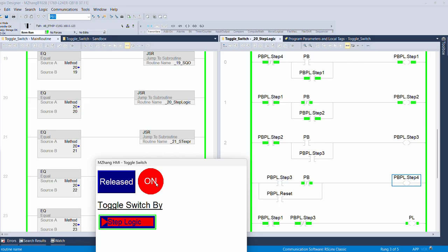It stays on, and after you have step 2, before you go to step 3, you need to press again. It's waiting for the second press. When you press, step 3 turns on, and when I release, that goes into step 4, and step 4 will reset the whole thing, so you can continue to use the same design for the following operations.